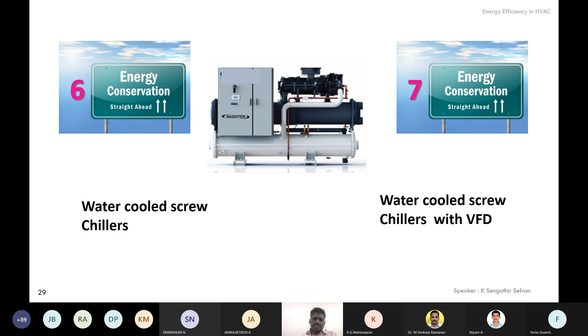With the VFD, you can see after 80% the specific power consumption comes down drastically, and the difference is much more when your ambient temperature is lower. Nowadays many chiller manufacturers are making VFD a default option. Of course, VFD brings side effects like harmonic generation, so it is very important to consider sufficient capacitors or harmonic filters so that power quality is maintained at the load, without compromising the upstream electrical infrastructure.